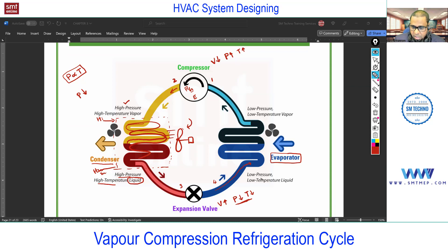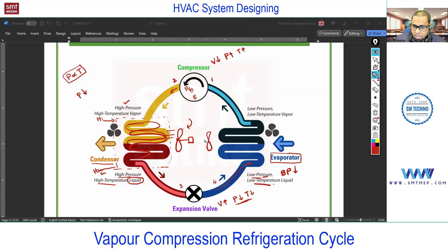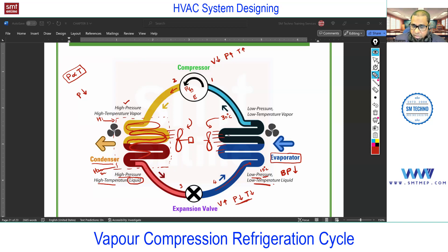When low pressure and temperature refrigerant enters the evaporator, because of low pressure the boiling point of that refrigerant also reduces, meaning it can start boiling at low pressure when extracting heat. For example, in an air conditioner, a fan sucks air from the room — say room temperature is 30°C and refrigerant temperature is say 5 to 15°C, depending on capacity and other factors. When 30°C air is thrown on the coil, the air does not mix with the refrigerant — there is no mass transfer. The copper tubes are good conductors, so the surface of the copper tubes cools down.